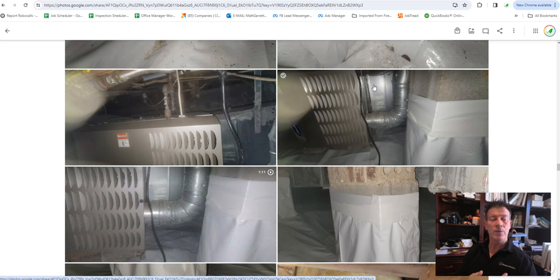keeping the fire going. And now it has to pull from the home. So it has to deprive the crawl space of oxygen and suck air from the home. So now it's struggling, eating up more energy trying to work. That's why North Carolina building code's minimum is for knucklehead contractors. So the minimum is to put in the 2 inch pipe going to an outside foundation vent that allows the furnace to suck in air so it can breathe properly and stay highly energy efficient.